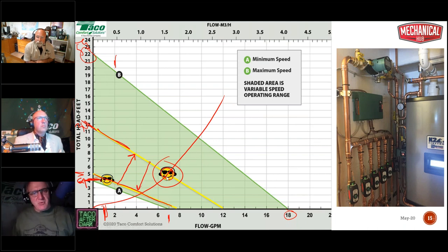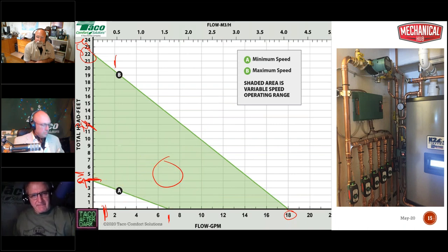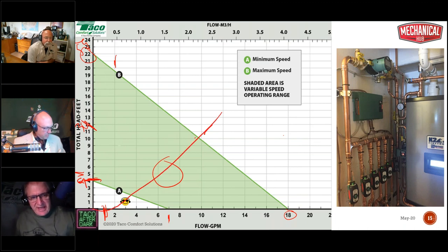Now, here's where the minimum speed comes into play. Let's say we're at 50% load. That's 3.5 gallons a minute, 35,000 BTUs. As we follow out our system curve, 3.5 gallons a minute is a little over a foot of head. Well, because we have a minimum speed, we can't work there. So where does it work? It works where the system curve intersects the pump curve, which in this case is right here. It's going to work at about 4 gallons a minute. Guys, we're not going to have a 20 degree delta T then. It's just not going to happen.